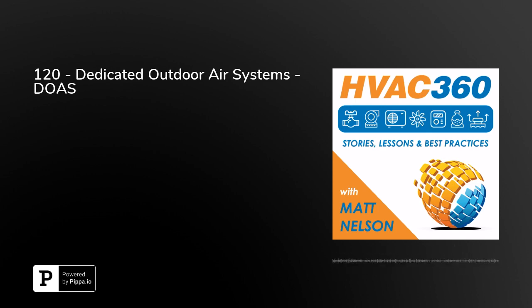So I guess at what point does a DOAS make sense? Now, I've heard it said that when your sensible load is about 70% or more of your total load, that's when you want to use a DOAS system. Now, a DOAS system basically does a better job and saves more energy on latent and sensible cooling than your more traditional units. A lot of this has to do with energy recovery, but that doesn't necessarily always have to be the case.